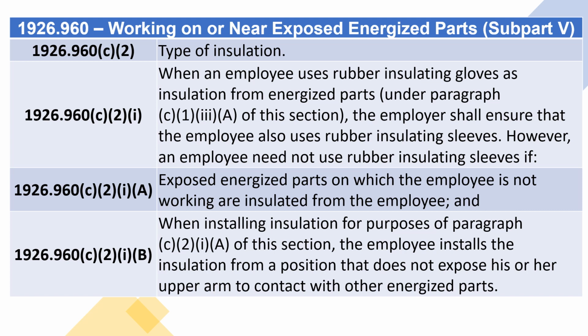1926.960(c)(2) When an employee uses rubber insulating gloves as insulation from energized parts, under paragraph (c)(1)(iii)(A) of this section, the employer shall ensure that the employee also uses rubber insulating sleeves. However, an employee need not use rubber insulating sleeves if 1926.960(c)(2)(i)(A) through (c)(2)(i)(B) exposed energized parts on which the employee is not working are insulated from the employee, and when installing insulation for purposes of paragraph (c)(2)(i)(A) of this section, the employee installs the insulation from a position that does not expose his or her upper arm to contact with other energized parts.